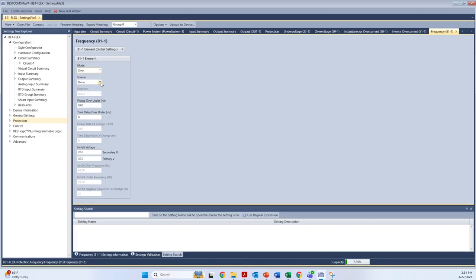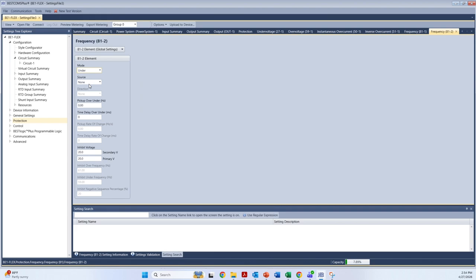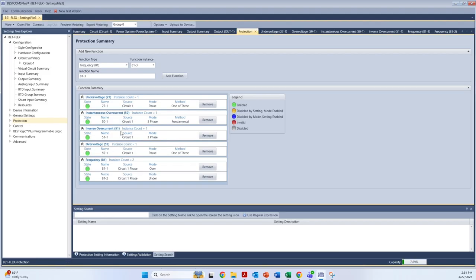So we'll do the over frequency next, feeder 1. And again, a small time delay, and it automatically has an inhibit in there for you if you want to use that. Use the under. Put in the setting. And a small time delay again. And then I have all the settings put in for the different elements.